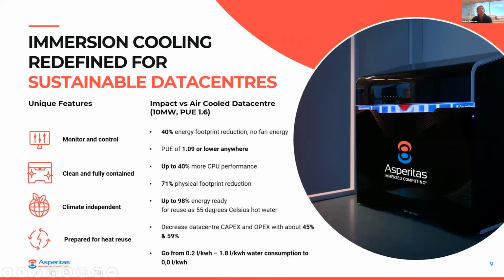So just to look at a case - I think we should see this as an industry as a great opportunity to see what we can do about the still-global average PUE of today. In the last few years it's maybe gone in and out between 1.5 PUE up to 1.6 in the last 3 years, following the uptime reporting on that topic. If we take the 1.6 global average, just to keep things simple, you can see on screen quite some benefits there - a huge energy footprint reduction, not only on the cooling side.